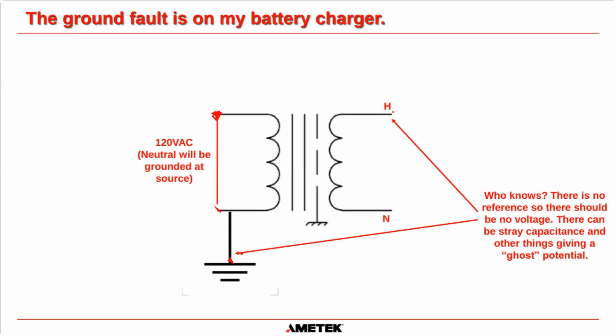It's as if the secondary of this transformer has no idea where ground is. It is just floating in the ether and has no idea whatsoever where ground is. It doesn't care where ground is on this simple transformer, okay? It does not care whatsoever. It doesn't need ground to operate. All it needs is a hot and a neutral, or a live and a neutral.